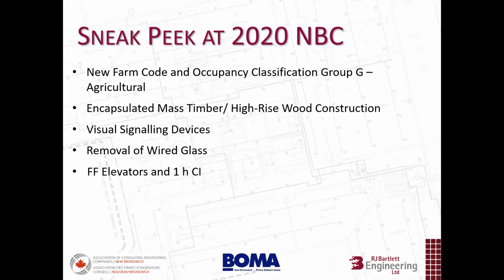Some new requirements for visual signaling devices. They previously had specific areas where they required visual signaling devices, but that's becoming less popular, as other jurisdictions have basically said it's better to just provide these, and not only where there may be hearing impairments and things like that, but it's a relatively inexpensive life safety device, and it's seen as a valuable one. So they're increasing the areas in which they're going to require visual signaling devices. The removal of wired glass is finally going to find its way out of the code. For those of you not aware, there have been some case studies where individuals have tried to break through this wired glass. And what happens is the glass may break, but the wires within become quite sharp and end up cutting individuals.